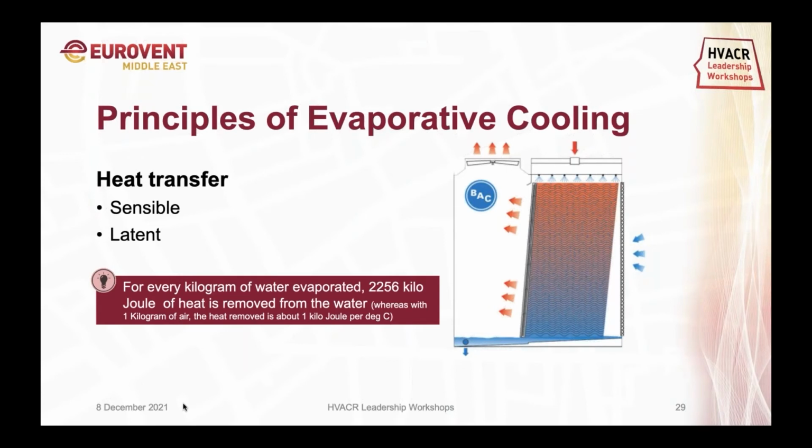What happens in evaporation is that there is an interaction between water and the air, and approximately 1% of the water gets evaporated. For converting the water from its liquid phase to the vapor phase, we need approximately 2300 kilojoules of heat per kg of water. That is why the remaining water gets cooled, and that is why we see that T out is much lower than T in when we look at the cooling tower.